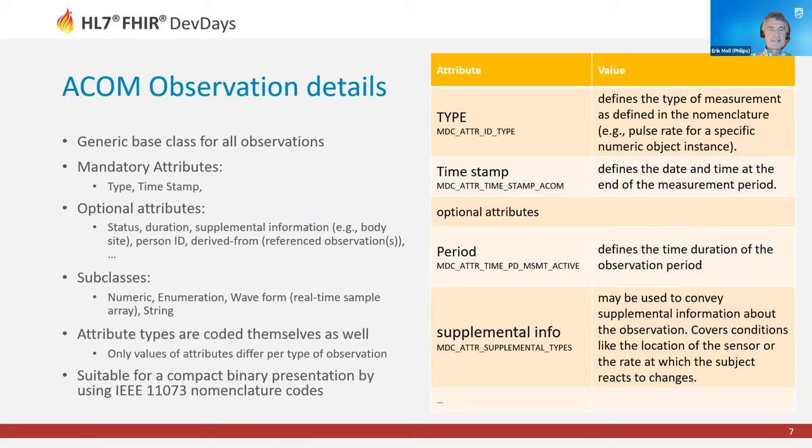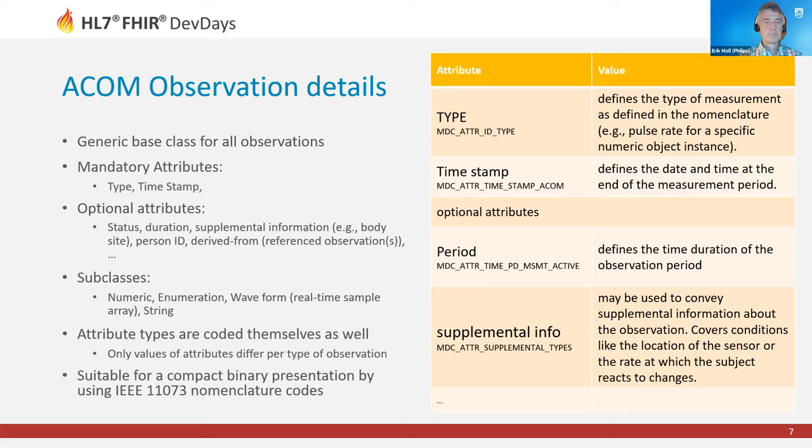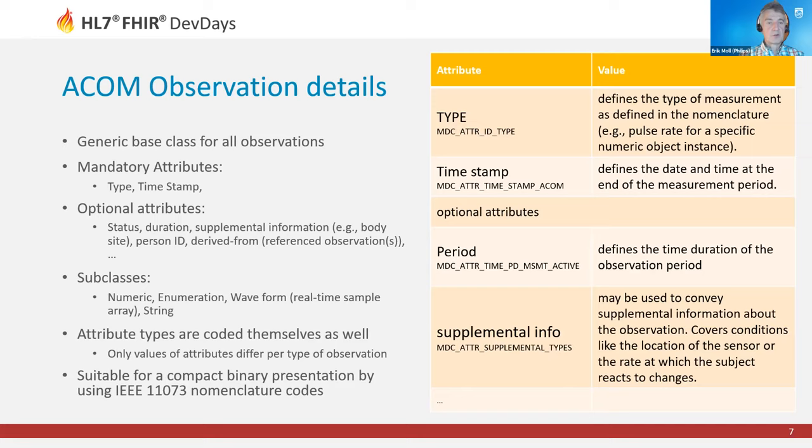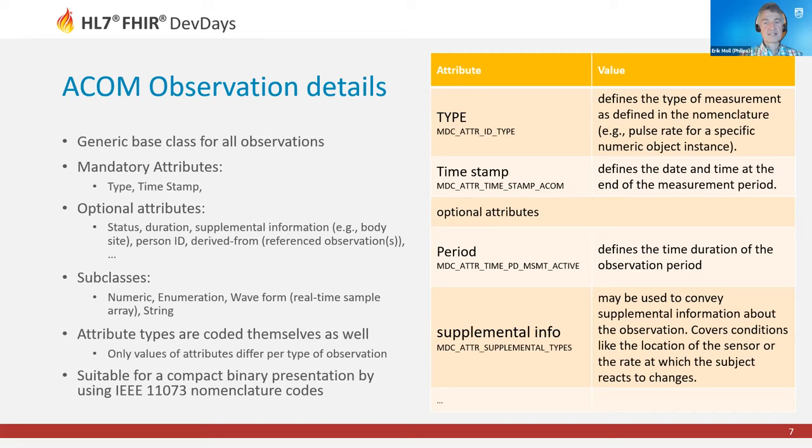Zooming further into this observation class, it's the generic base class for all observations. It has a number of mandatory attributes: a type that defines the kind of measurement being reported, the timestamp, and a number of optional attributes such as the observation status, the duration, supplemental information, a person ID and references to other observations. The nice thing about this model is that the attributes come with an MDC code from the IEEE 10101 nomenclature set. That enables a compact binary representation of both the attributes and their values.